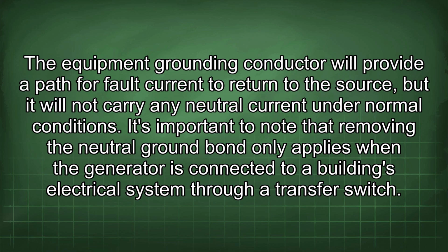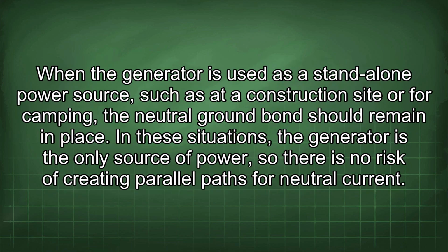It's important to note that removing the neutral ground bond only applies when the generator is connected to a building's electrical system through a transfer switch. When the generator is used as a standalone power source, such as at a construction site or for camping, the neutral ground bond should remain in place. In these situations, the generator is the only source of power, so there is no risk of creating parallel paths for neutral current.